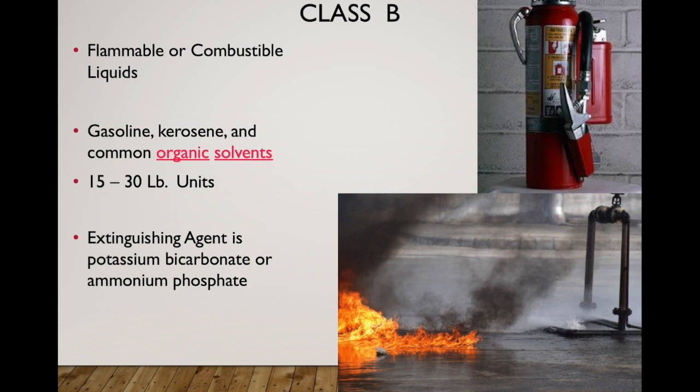Our typical extinguishing agents are a dry chemical powder made up of potassium bicarbonate or ammonium phosphate. Another important consideration when dealing with a flammable or combustible liquids fire is to try and contain that fire prior to extinguishing. It's going to help with the actual extinguishment itself, versus if the fire is somewhat three-dimensional or cascading down a set of stairs or objects where it's harder to put it out.